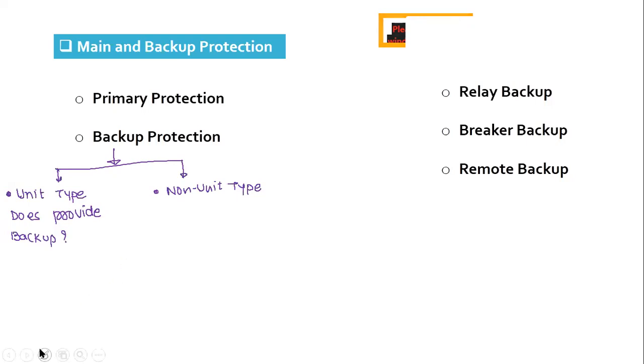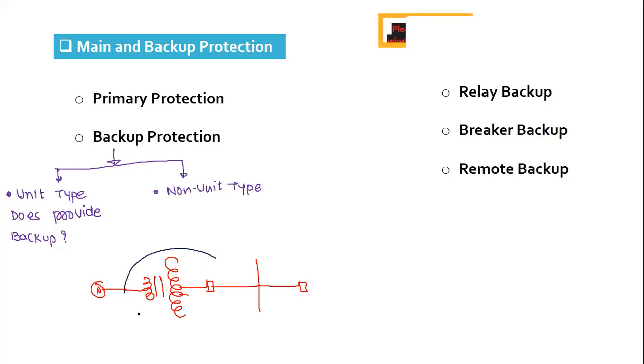Correct, Niti. Suppose it's not clear, let me explain with the same example we have taken. Suppose here we have a transformer protection zone which operates in this region, and a bus bar protection zone which operates in this zone. Suppose there is a fault on the bus bar, will this transformer protection give backup or not?